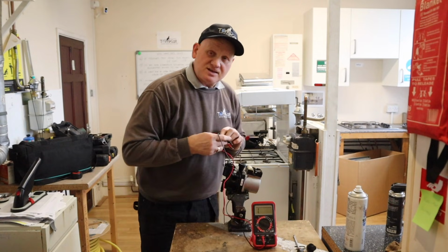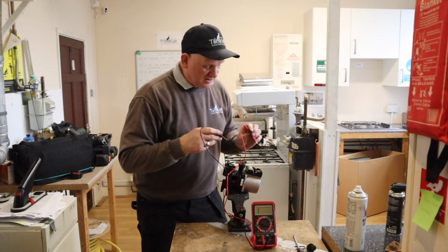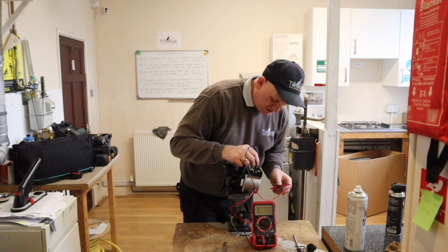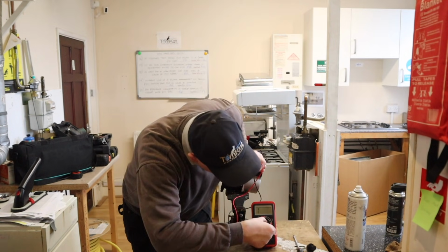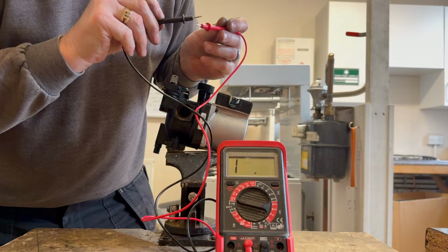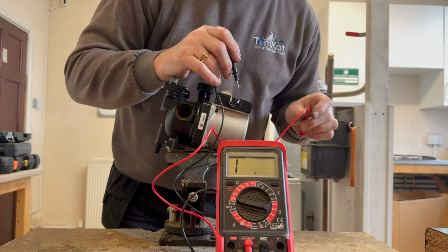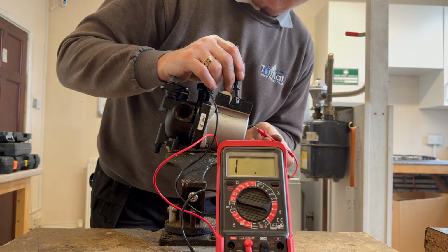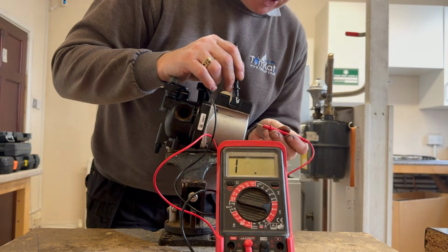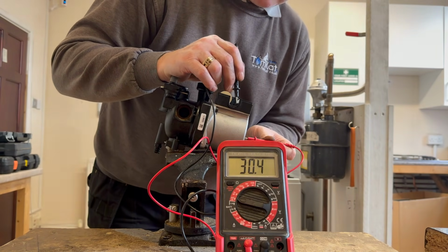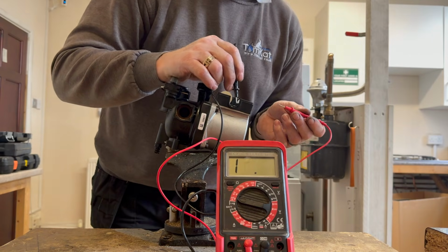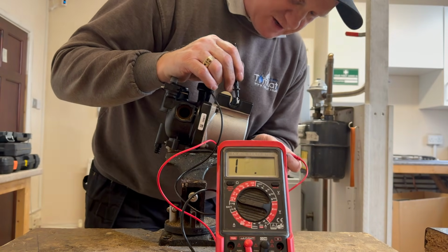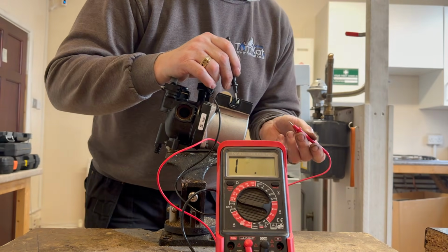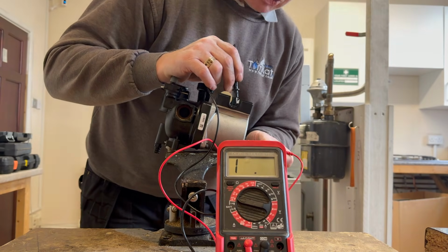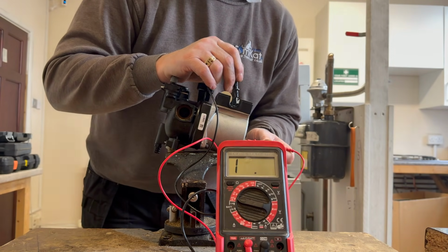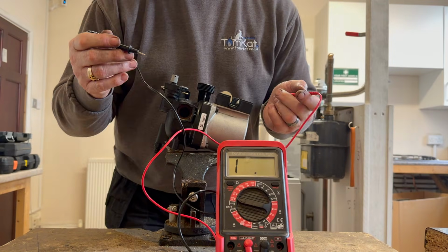Now I can test whether we've got a dead short. I need to turn it onto the buzzer first to make sure that's working. If I go on the earth terminal and then to the screw in the centre, I should get a buzz, which I do. And if I go to my neutral and the earth screw, I shouldn't. And if I go to the live and the centre of the screw, I shouldn't. So I haven't got a dead short. This pump looks good.